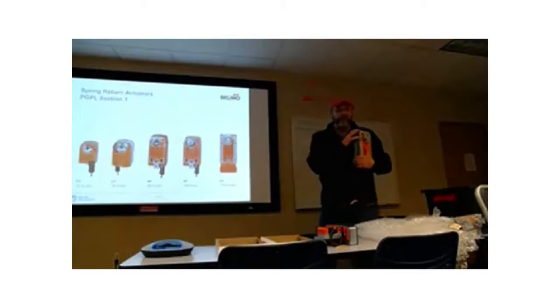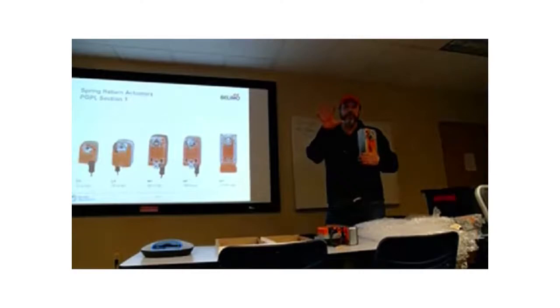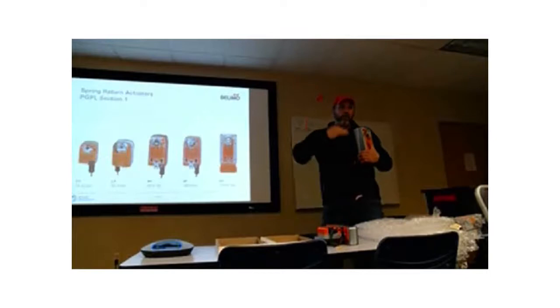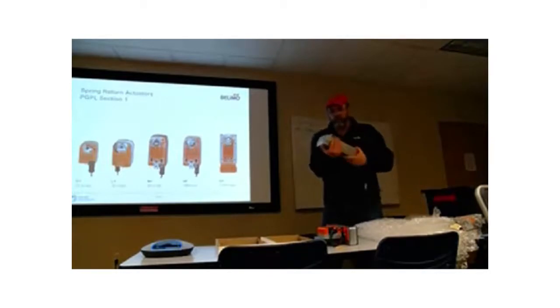These actuators are pre-tensioned when shipped in the box. If you follow the instructions and seat this actuator on the shaft, you seat it and close it, keep it closed. When you turn the power on, it releases and will go seat the damper blade. That's about another 5 degrees of rotation, so make sure that damper seal is tight. That's how you install it to make sure the dampers operate properly.